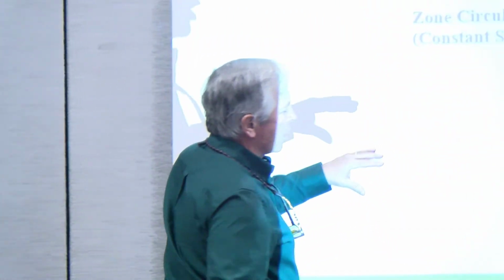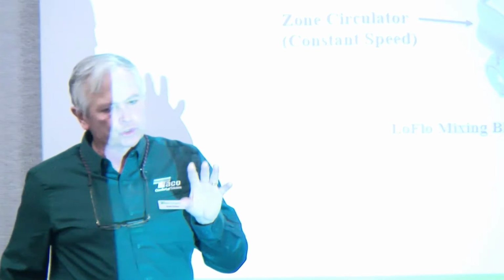So we're injecting, it's injection pumping, excuse me. Some of you are probably familiar with that, with other types of setups. So that's a variable speed one. It ramps up very slow, it injects it right in until that return water gets back down to where it has to be. So that's the type of thought process we have. And when you install this type of system with our controls, we've seen first cost go anywhere from 20 to 40% less. With the controls, 20 to 40% less. It depends on the project.